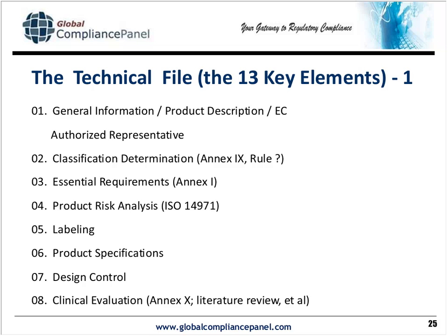Product specs, design control, again, as we mentioned under 7.1, etc., in the Medical Device Directive / ISO 13485. And then clinical evaluations. Here's where the FDA is slowly moving toward the European model. Under the European model, your clinical evaluation can basically be a literature review. If your product is somewhat of a Me Too product, there's a lot of history out there already published by doctors and researchers regarding your product and its interaction with a patient.